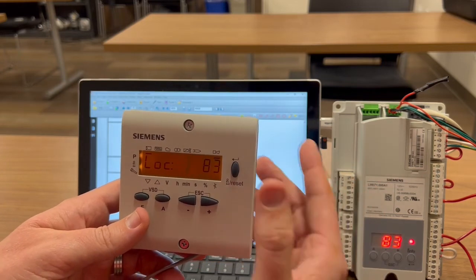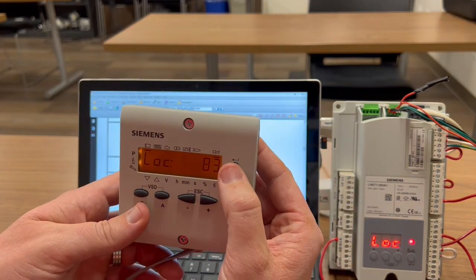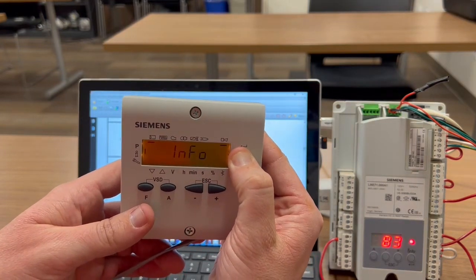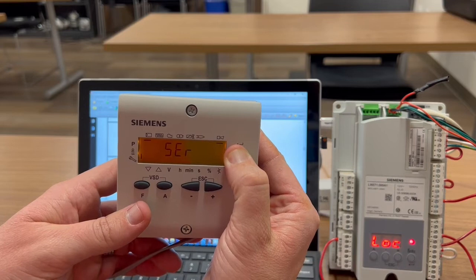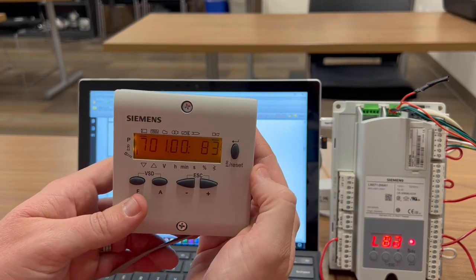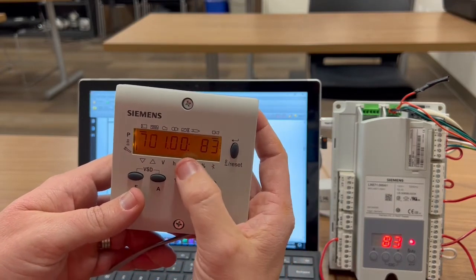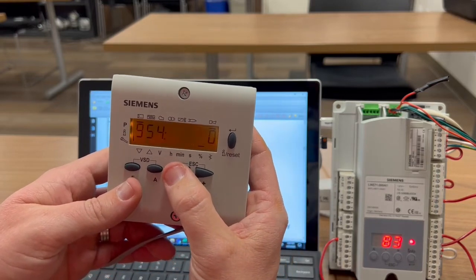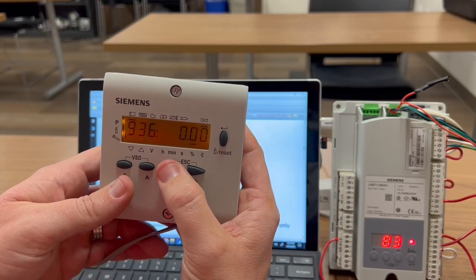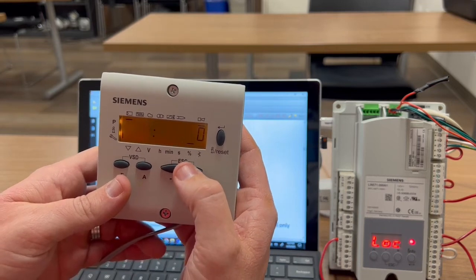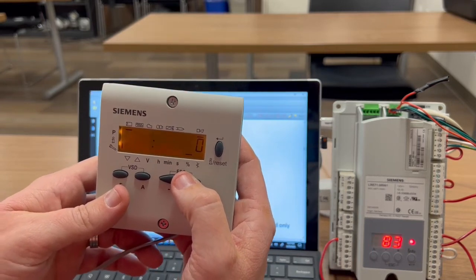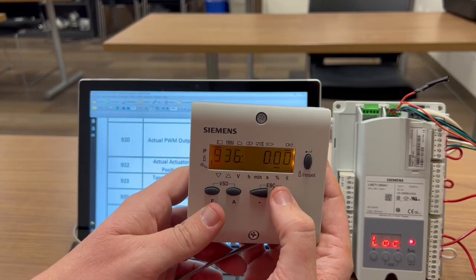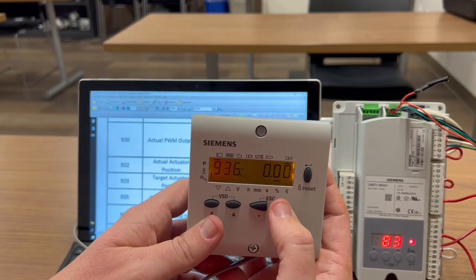Let me show you how to get into service mode. Take the enter button, press and hold until it reads SER for service mode. Let go. It starts with the 700 series, which is the fault history. I'm going to go back and go to 920. 920 reading actual PWM signal and 936 is the actual speed.